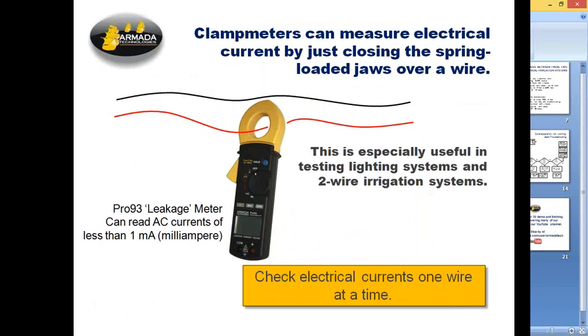So the clamp meter, again, one of the tricks, we sell several varieties of clamp meters, and this is the Pro 93 for the two-wire, the most expensive and the fanciest, but they all work by clamping over one of the pair of wires. Now, we've got two wires going out into the field in a two-wire system, obviously, so we got to clamp over one of them, and we can read, without interrupting anything, the amount of power being fed to the field through this. I can also go back up to the controller, plug the test leads into this, and read the voltage going into the field, which is one of the first things you do. But out there, clamping over the wire, very good, non-invasive way of finding out if the power is flowing up from box to box down the chain as you expect it to.